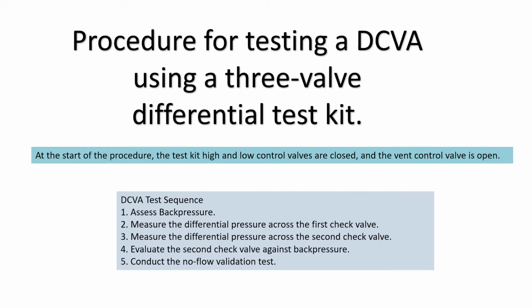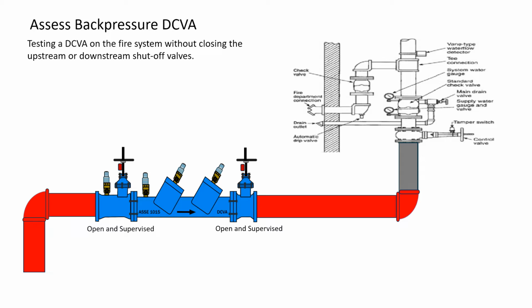1. Assess back pressure. 2. Measure the differential pressure across the first check valve. 3. Measure the differential pressure across the second check valve. 4. Evaluate the second check valve against back pressure. 5. Conduct the no-flow validation test. Assess for back pressure, DCVA.